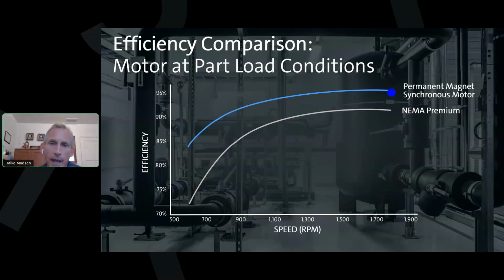But what happens is the IE5 motor has a more flat efficiency curve. It stays high longer. And we know whether we're doing domestic boosting, a heating water application, a chilled water application, we spend a lot of our time operating at part load. And so at part load conditions, the energy savings are even greater with the IE5 motor. So we spend a lot of time operating down here, and so we're actually able to generate more than 7 to 10% energy savings. So it's a quick and super easy approach to reduce your power consumption in your designs.